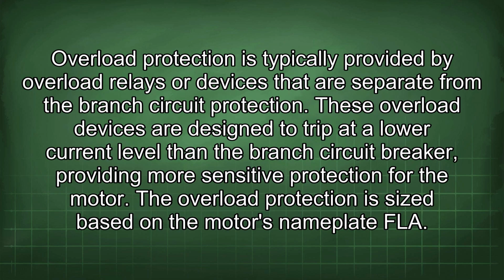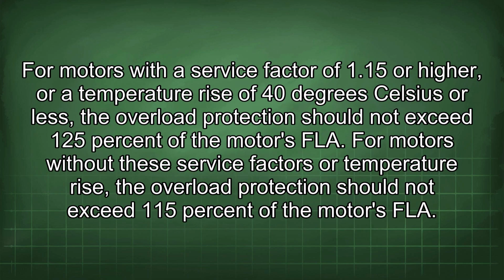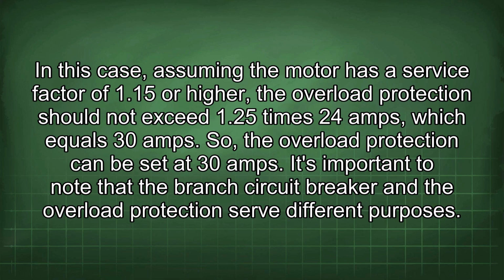Overload protection is typically provided by overload relays or devices that are separate from the branch circuit protection. These overload devices are designed to trip at a lower current level than the branch circuit breaker, providing more sensitive protection for the motor. The overload protection is sized based on the motor's nameplate FLA. For motors with a service factor of 1.15 or higher, or a temperature rise of 40 degrees Celsius or less, the overload protection should not exceed 125% of the motor's FLA. For motors without these service factors or temperature rise, the overload protection should not exceed 115% of the motor's FLA. In this case, assuming the motor has a service factor of 1.15 or higher, the overload protection should not exceed 1.25 times 24 amps, which equals 30 amps. So, the overload protection can be set to 30 amps.